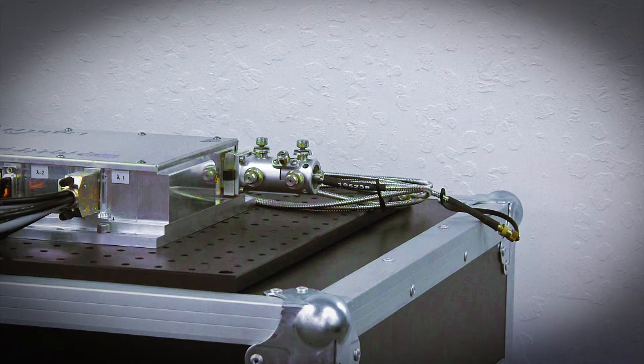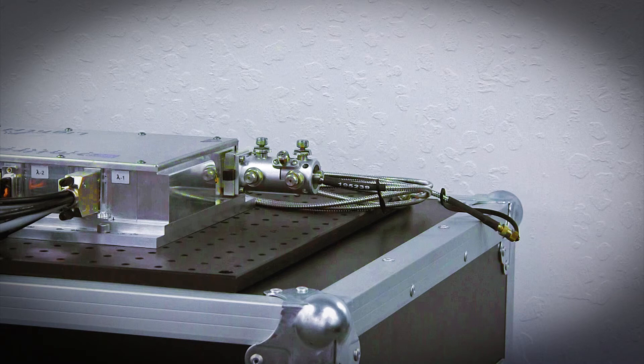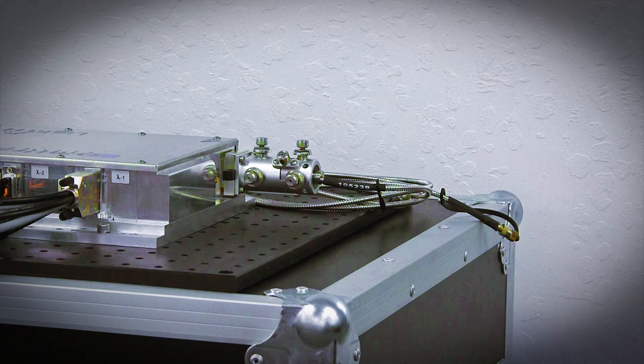Finally, we are ready to install the fiber optic cable. For this configuration, a polarization maintaining single mode fiber with FC/APC termination is used. Other types of fiber configurations are available, depending on your particular requirements. Please note there is a shutter on the output of the Light Hub that should be in the closed position before installing the fiber optic or turning on the Light Hub itself.